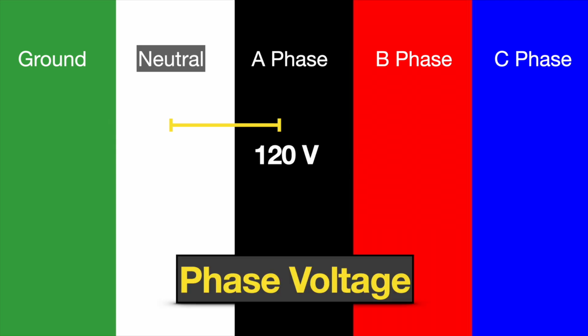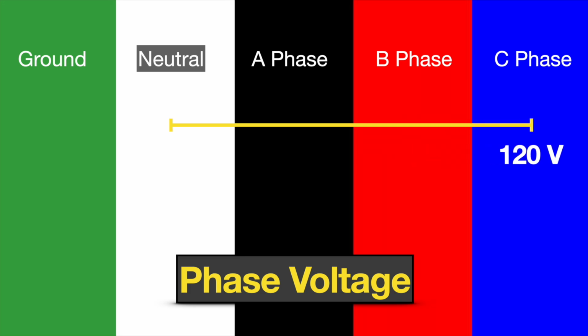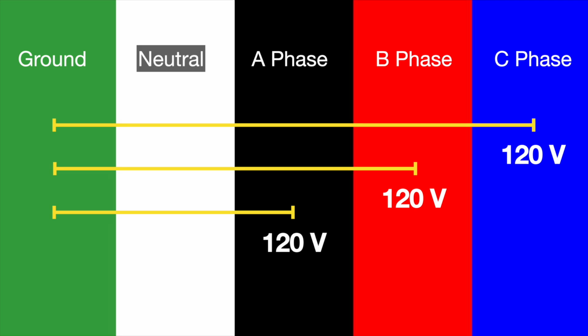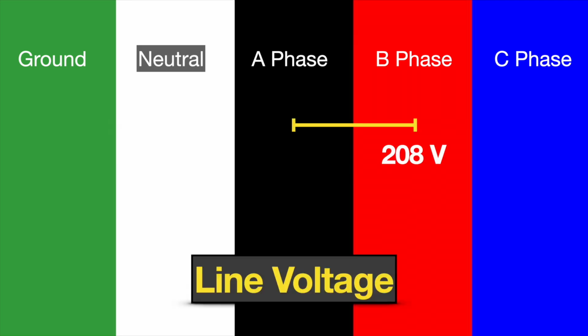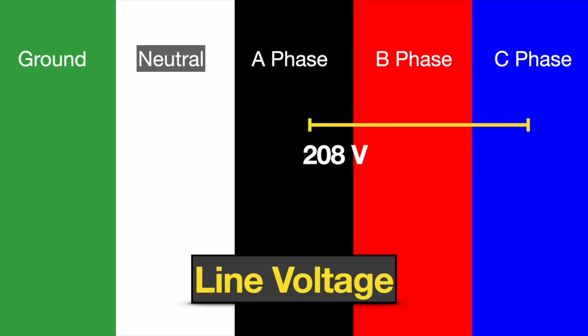Now let's move on to phase voltage. You would measure between neutral and the black A phase, should read 120 volts. Neutral to B, the red phase, should also read 120 volts, and neutral to C, the blue phase, should be 120 volts. That's called phase voltage. If you measure ground to each of the phases, they should also read 120 volts. Line voltage is what's referred to as phase to phase: black to red should be 208, red to blue should be 208, and blue to black should be 208 volts.